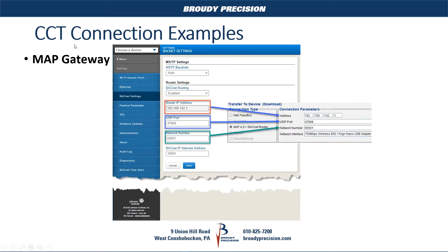For a MAP gateway example: in the MAP gateway, under the BACnet settings, you'll find your MAP's IP address, the UDP port, and your network number. Those are the fields you'll take and use in CCT. As you can see, these are the values. There is a button that says MAP gateway — you can click that and it automatically fills in that information. Then your network interface, since this is Wi-Fi, would be your Wi-Fi connection.